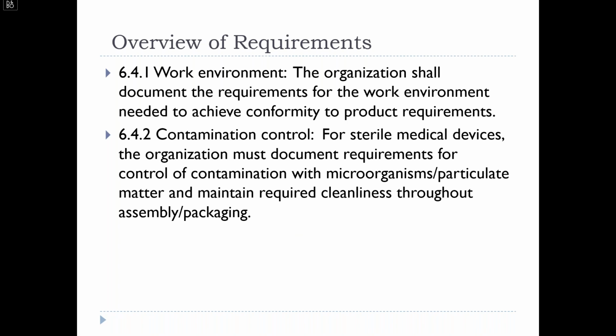6.4.1, more about the work environment. The organization shall document the requirements for the work environment needed to achieve conformity to product requirements. Does the product need to be processed in a clean room? Are there temperature, humidity requirements, certain PPE requirements?